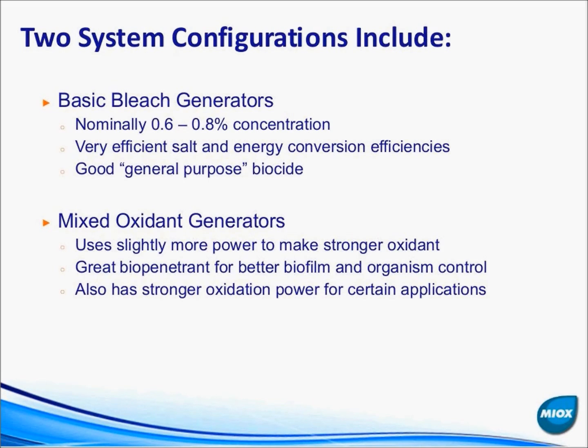We make two system configurations. The first is a basic bleach generator, which produces approximately 0.6 to 0.8 percent solution depending on the equipment. These are strictly designed to generate the maximum amount of bleach for the lowest price possible — simple sodium hypochlorite generators designed to run at maximum efficiency.